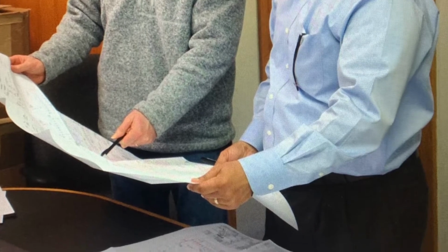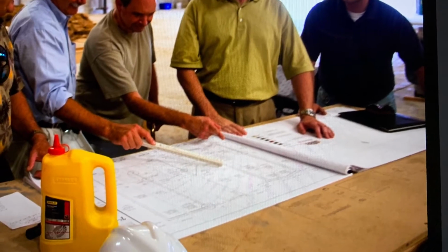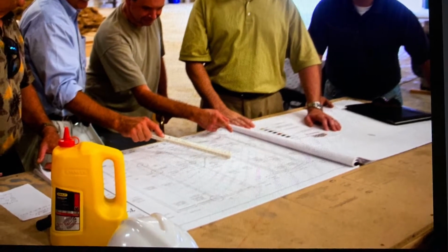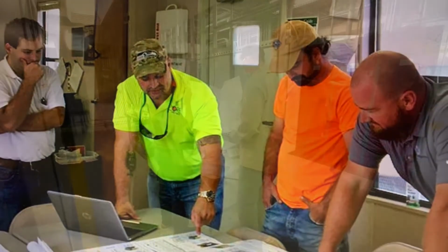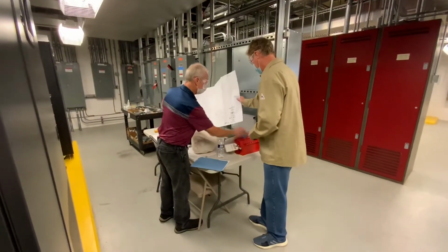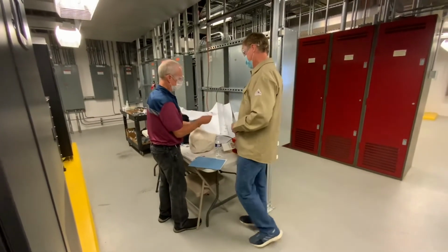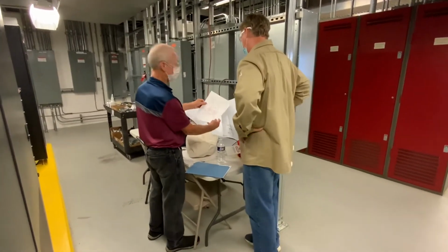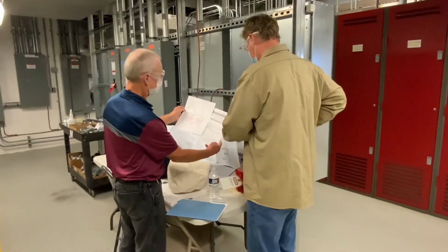Here are some of the key elements of a job briefing when discussing with employees. Identify the electrical hazards, both shock and arc flash, associated with the job or task. What are the work methods or procedures that one must consider? Are there any special precautions that need to be considered? For example, are you working with capacitors, which require additional safe work practices to ensure that they're safe to work on? How are you controlling the energy source? Is a lockbox required? What PPE is needed to perform the task safely?